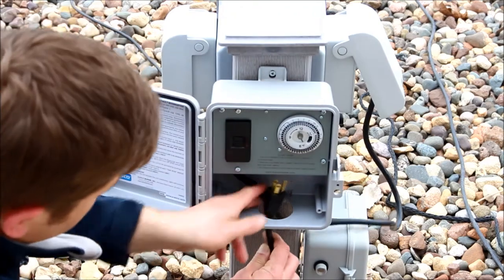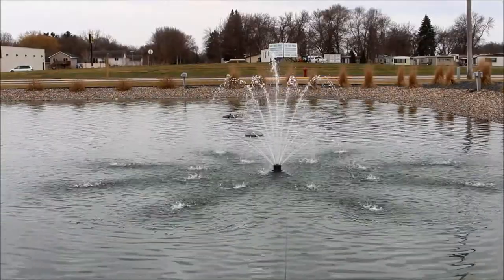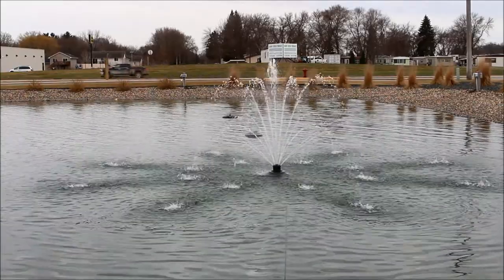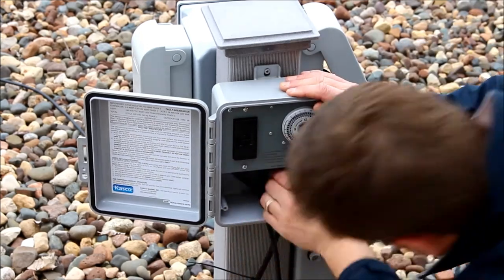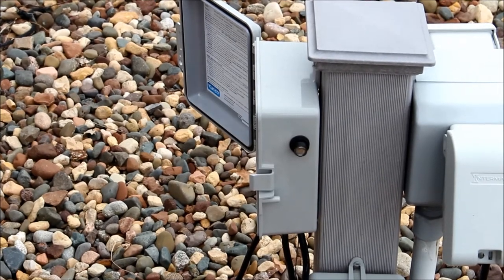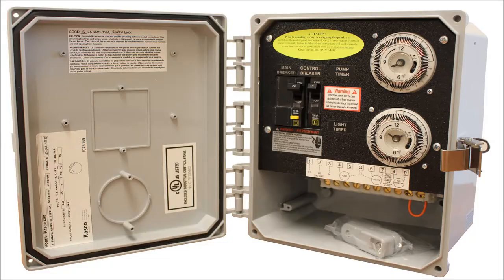Plug the fountain or aerator into the control panel, ensuring the timer is in an on position, or into a GFCI receptacle, and reset the GFCI. If the fountain or aerator trips, then further testing is required to determine where the problem may be. If the unit runs fine, move to testing the lights. Next, unplug the fountain or aerator and plug in the lights. If using a Kasco C25 controller, you will need to cover the photo eye with electrical tape for at least 60 seconds to activate the photo eye. If using a C85 or C95 controller, simply ensure both timers are in the on position.